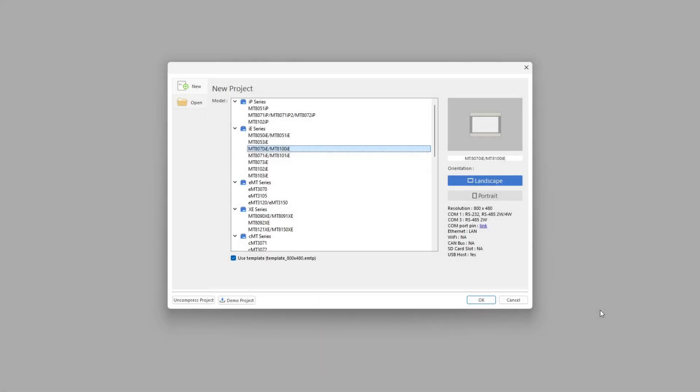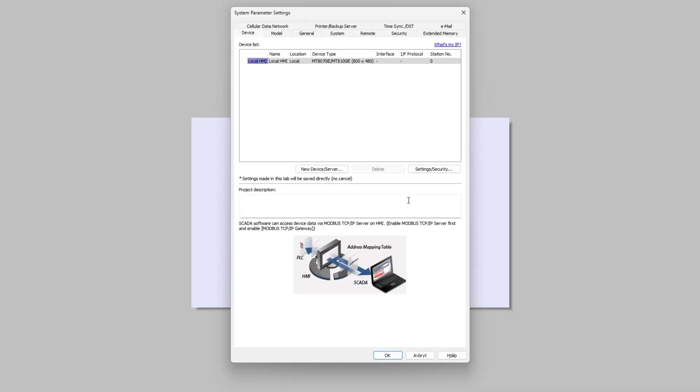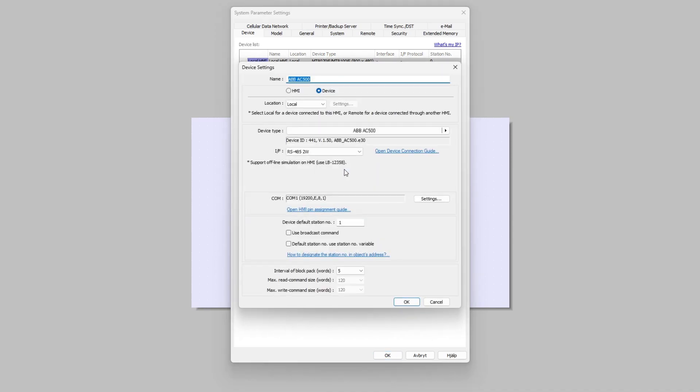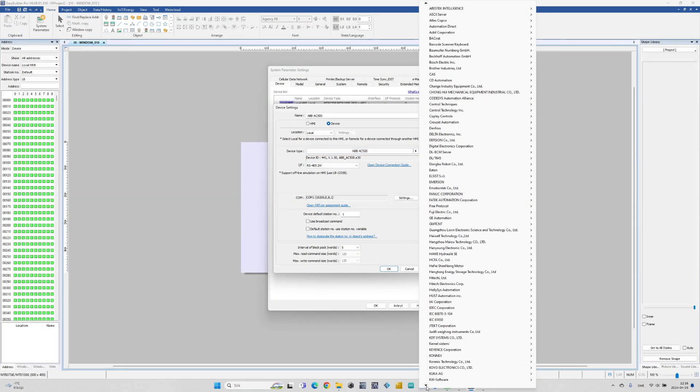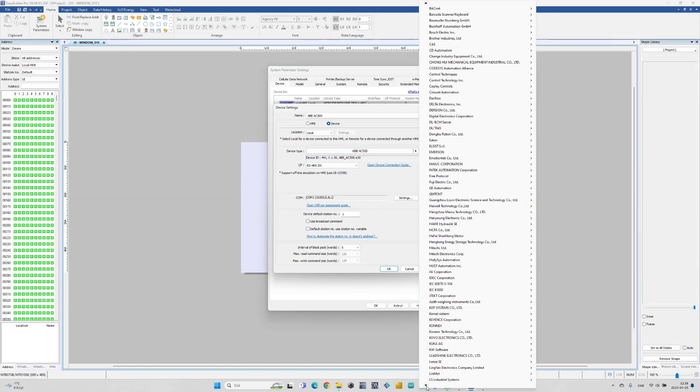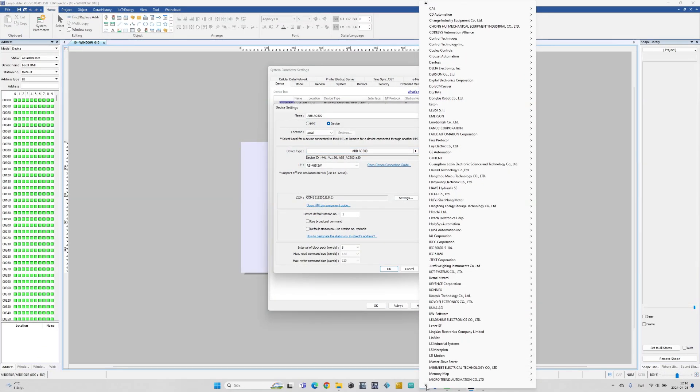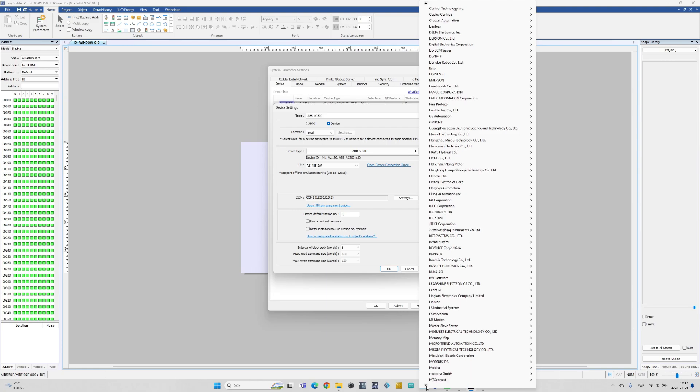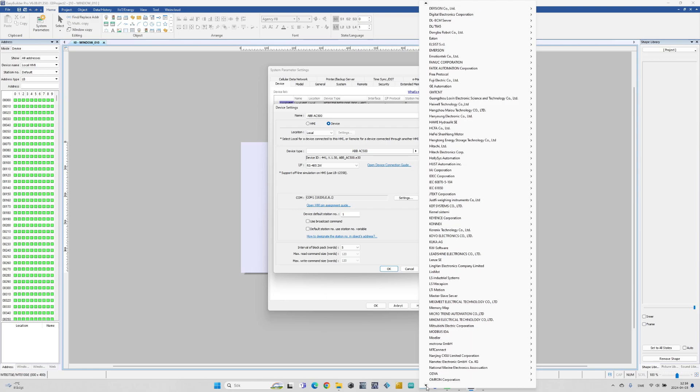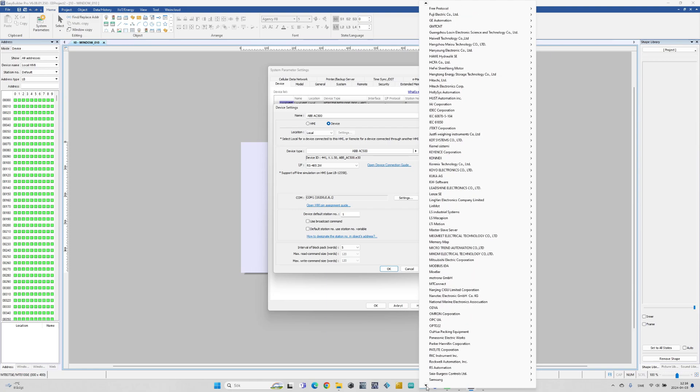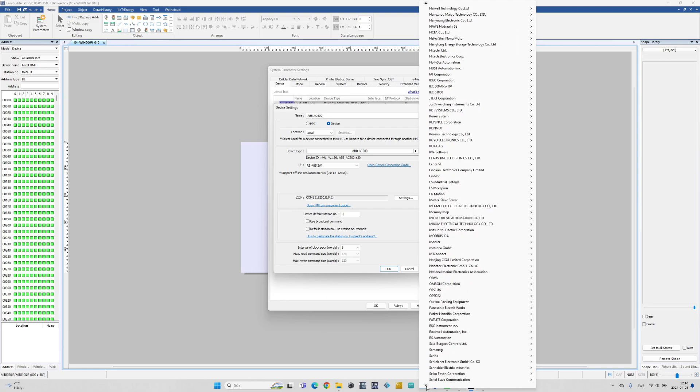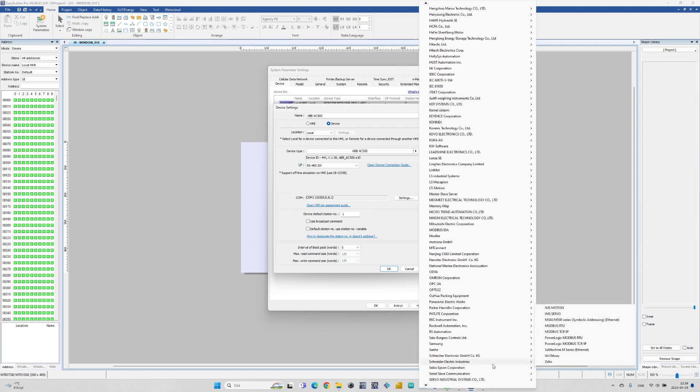Now let's do the HMI side of things. First choose the correct HMI you are using. Then in the System Parameter settings we want to add our PLC. To do so we click on New Device. Then we choose the correct device type. Under the Schneider Electric Industries tab we choose Modbus RTU.